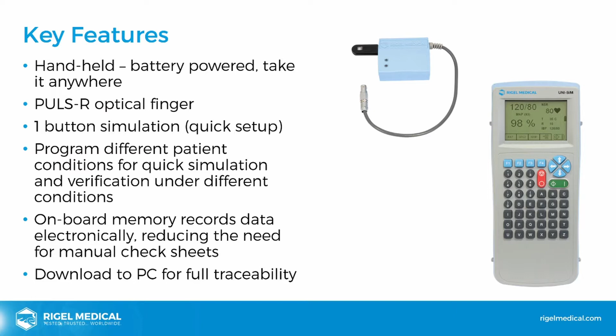Simply hit the green button and those preset patient simulations will be utilised. So you can program different patient conditions for quick simulation and verification under different conditions. We've got onboard memory, which records data electronically, reducing the need for manual check sheets, and downloadable results to the PC for full traceability. The onboard memory records, this is not available in the manual mode, automatic mode only, but I'll go into that in the demonstration, go into a bit more detail.